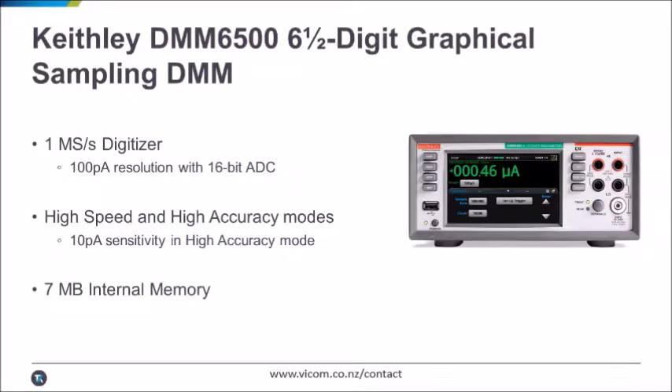A Keithley DMM6500 is a great low-cost solution for this measurement. It features a 1 mega sample per second 16-bit digitizer with a minimum resolution of 100 picoamps. If you need more accuracy, you can always operate in a high accuracy mode at a small speed sacrifice.